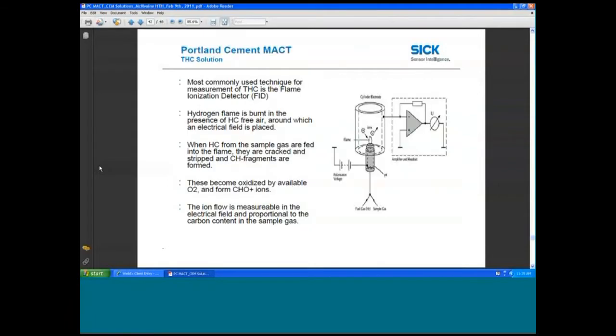Next slide. Total hydrocarbon. Typically, the most commonly used technique, of course, is the flame ionization detector. I won't go through the whole theory of operation of an FID. It's quite widely used and meets all the performance specifications of the PC MACT.